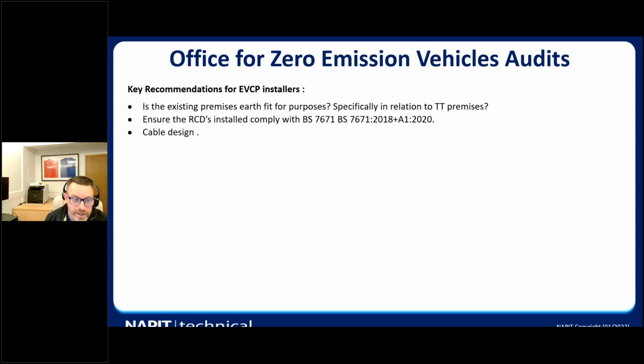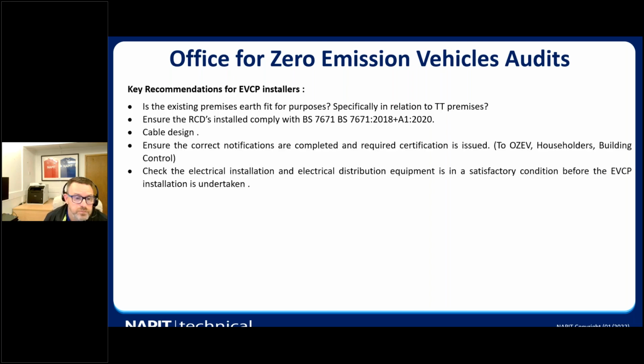Are the RCDs in compliance with BS 7671:2018? And that was obviously at the time of the audits, that was to Amendment 1 to 2020, which was the change to the EV installation. Looking at the cable design, making sure notifications are completed and where the required certification is issued to the DNO, to the householders and to building control. And the electrical installation and distribution equipment is in satisfactory condition before the EV charge point was undertaken.